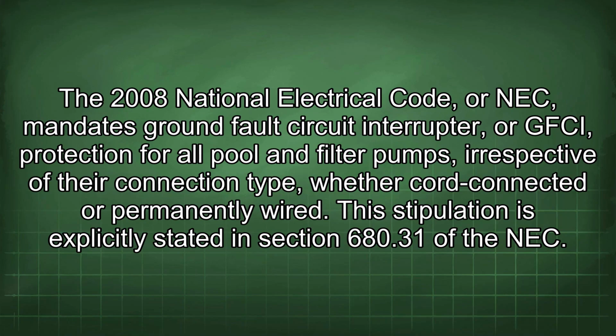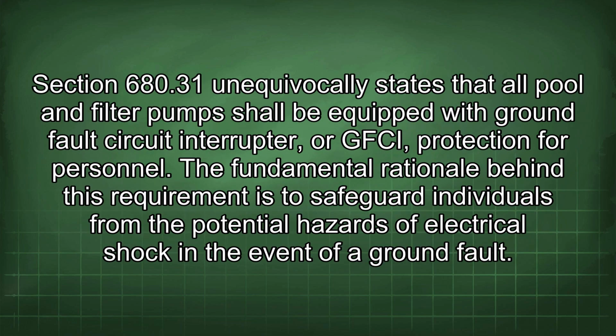The 2008 National Electrical Code, or NEC, mandates ground fault circuit interrupter, or GFCI, protection for all pool and filter pumps, irrespective of their connection type, whether cord connected or permanently wired. This stipulation is explicitly stated in Section 680.31 of the NEC. Section 680.31 unequivocally states that all pool and filter pumps shall be equipped with GFCI protection for personnel.